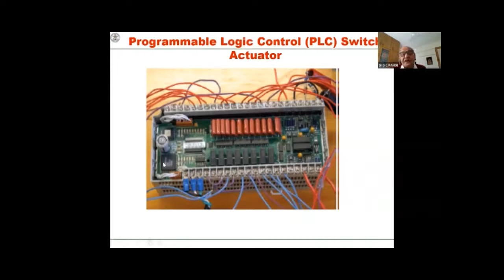For protection, we take into account how lengthy the cable is, what is the length, then we calculate the type of field that gets induced on that cable, and what type of protection is to be done on this particular cable. If it is fiber, it's fine. But after the fiber, inside there is electronic, there are PCB traces, there are some connecting cables and other things. They will pick up these fields, which are such a strong field that it may damage the system.